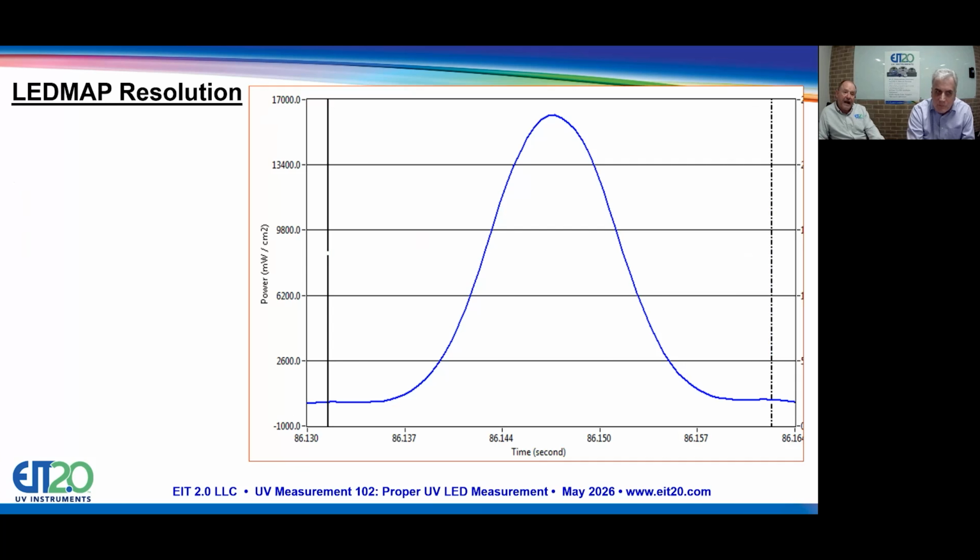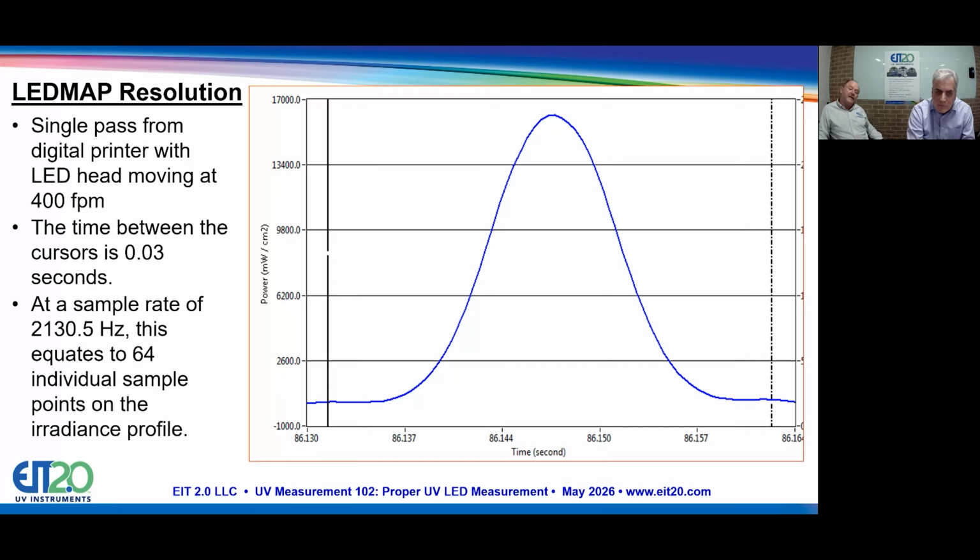This is actually looking at three hundredths of a second here, and we're able to get 64 individual sample points on that. So this is the type of information that gives you a lot more data than just a joule number or a watt number, especially if you have multiple LEDs. Jim, I agree, this is really important for people that always are asking, customers are always asking for more digital data as opposed to continuous monitoring. This will give them another leg up on their data acquisition and capabilities.